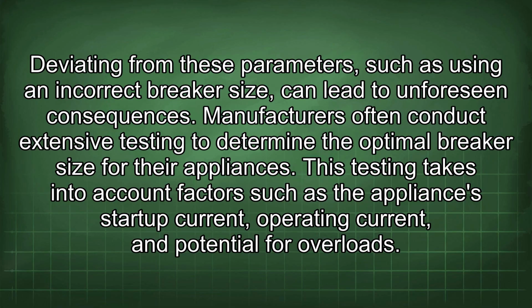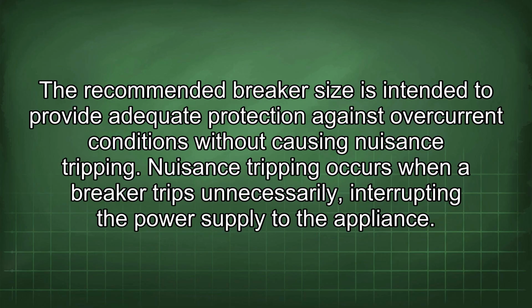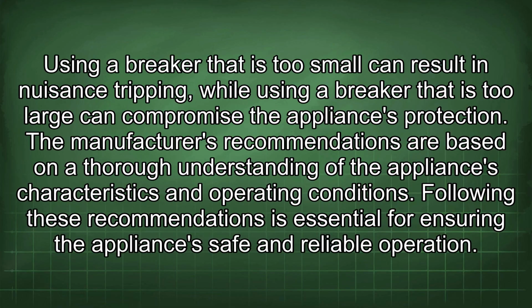Manufacturers often conduct extensive testing to determine the optimal breaker size for their appliances. This testing takes into account factors such as the appliance's startup current, operating current, and potential for overload. The recommended breaker size is intended to provide adequate protection against overcurrent conditions without causing nuisance tripping. Nuisance tripping occurs when a breaker trips unnecessarily, interrupting the power supply to the appliance. Using a breaker that is too small can result in nuisance tripping, while using a breaker that is too large can compromise the appliance's protection.